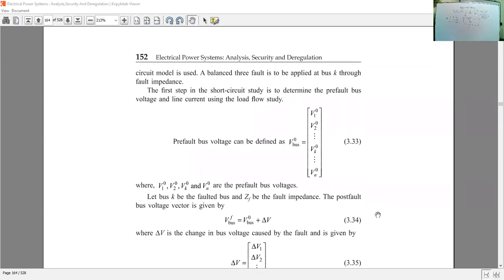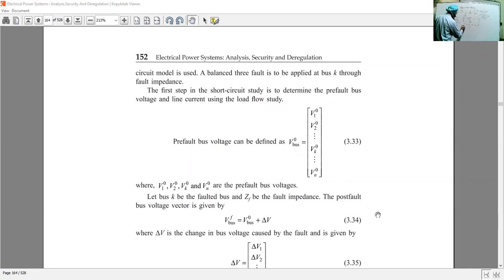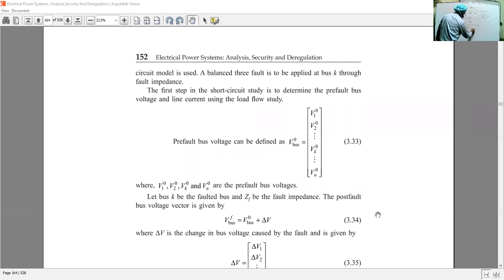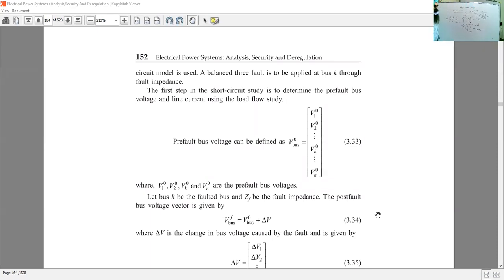This property is well applied in fault calculations. Looking at equation 3.33, we have the pre-fault bus voltages V_bus(0): V1, V2, Vk, and Vn, as an N×1 vector. Pre-fault bus voltages can be obtained from the load flow analysis, which is the normal conditions analysis of the power system.